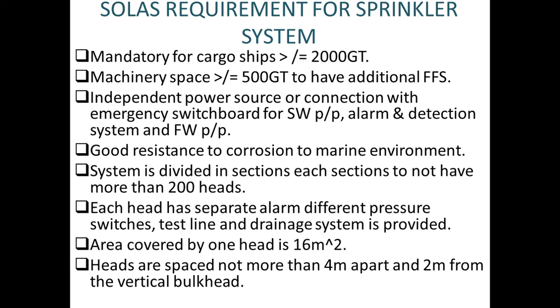Now when we talk about the sprinkler head, the area covered by one sprinkler head is 16 square meters. Heads are spaced not more than 4 meters apart. The distance between two heads cannot exceed 4 meters, and from the vertical bulkhead it should be 2 meters. So between two sprinkler heads 4 meters, and from the bulkhead to the head it should be 2 meters.